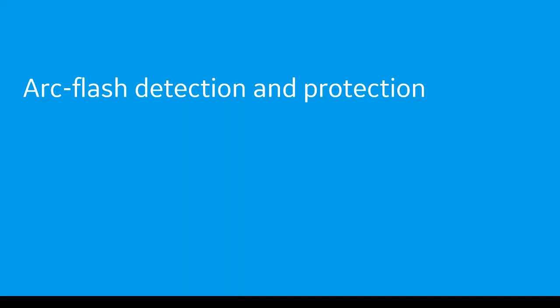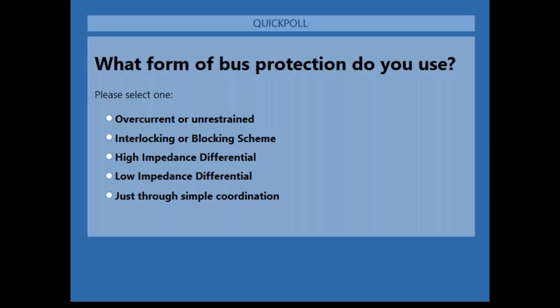Oh, yes. So we're going to talk about the protection techniques for arc flash detection and mitigation. One of the most effective ones is differential, specifically bus differential protection. So Mike's going to put a poll out there to see what kind of bus protection you use. One option is blocking. Another is that there's really no bus protection and you depend on coordination. Another is high impedance bus protection. Another is low impedance bus protection. And another is just unrestrained or overcurrent bus protection. That poll is out there, so please answer it if you can.